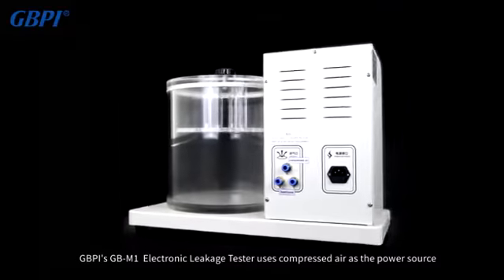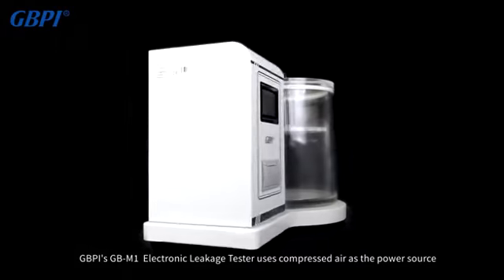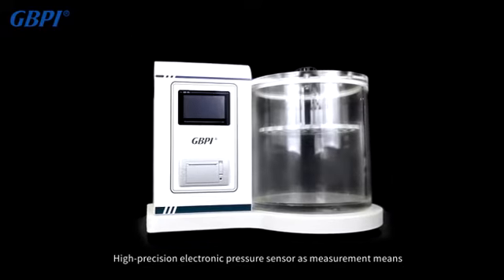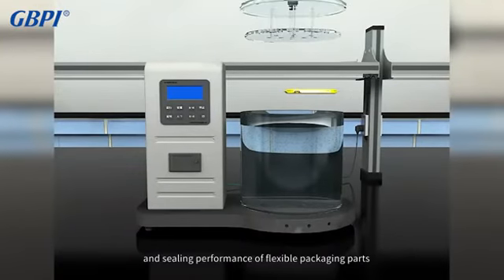GBPI's GB-M1 electronic leakage tester uses compressed air as the power source and a high-precision electronic pressure sensor as the measurement means. It can effectively compare and evaluate the sealing process and sealing performance of flexible packaging parts by evacuating the vacuum chamber.